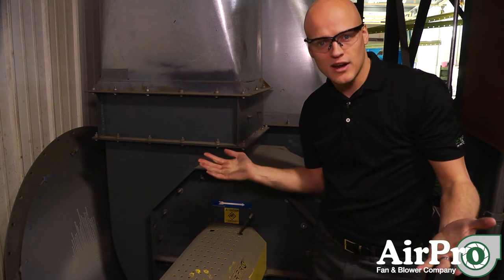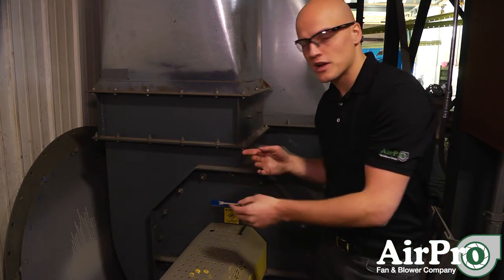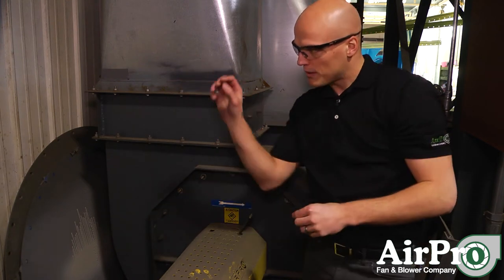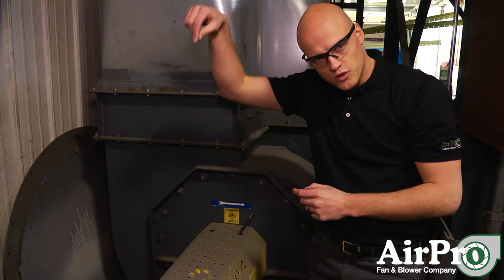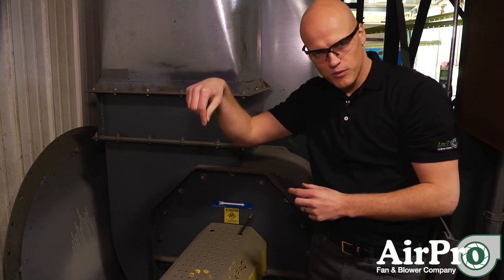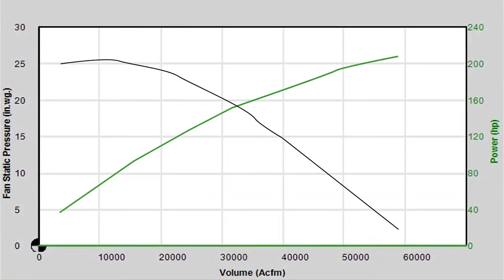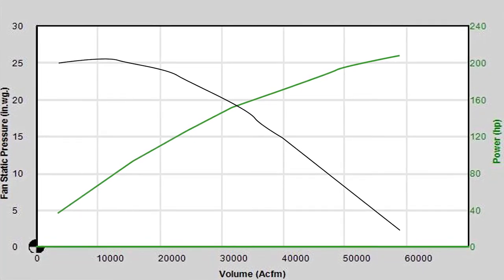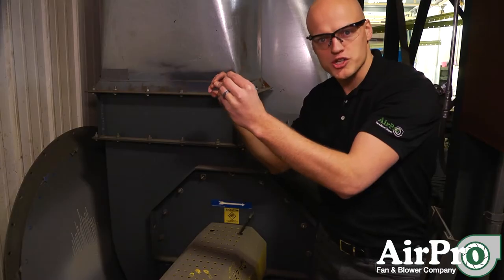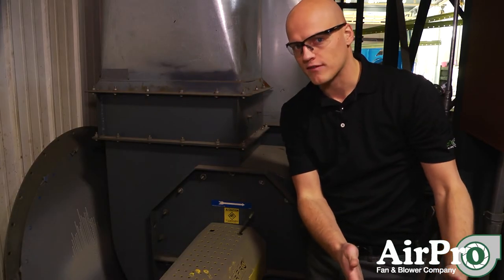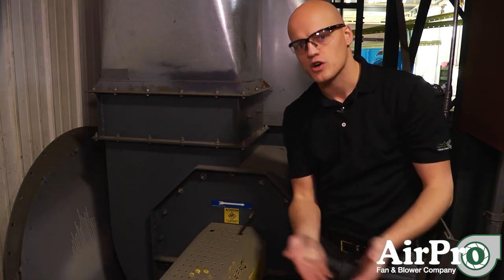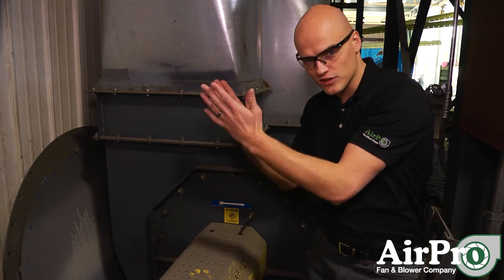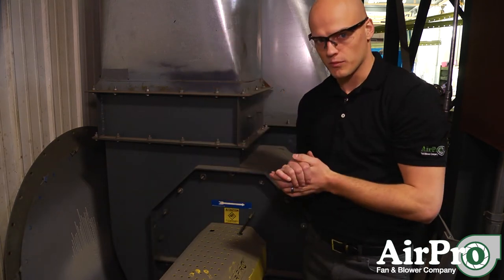In an ideal scenario you take your differential pressure — outlet minus inlet static pressure — and find that point on your curve. When you go vertically down from that point and it intersects the horsepower curve, take that point across to your horsepower legend on the curve. That number should line up with the amp draw you're getting off your motor. So convert your amp draw into horsepower — that number should line up on your curve in an ideal scenario with the static pressure differential you measured.